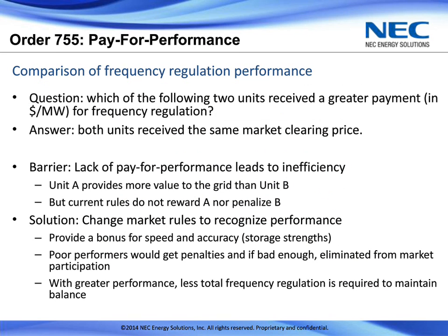Therein lay the problem: lack of pay for performance leads to inefficiency. While Unit A provided more value to the grid than Unit B, the rules did not reward A, nor penalize B. So the solution was to change the market rules to recognize performance, providing a bonus for speed and accuracy, which are strengths of energy storage. Poor performers would get penalties, and if bad enough, be eliminated from the market. Overall, with better performing assets doing frequency regulation, fewer total resources would be required, resulting in a more efficient and less costly way to balance the grid.